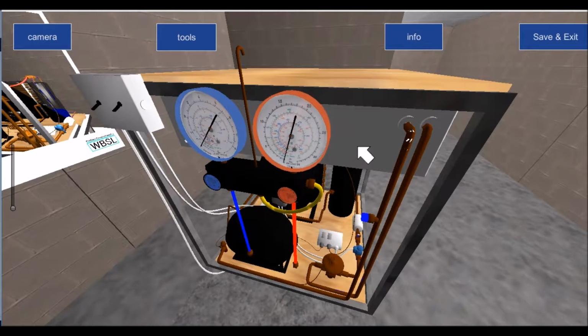So your evaporator then is the 4th component, and effectively what happens is that liquid is converted from a low pressure, low temperature liquid to a low pressure, low temperature vapor, and then it is superheated. In other words, the sensible temperature of the refrigerant is heated to a temperature above that of its saturation temperature. And basically that low pressure, low temperature superheated vapor is then drawn by the compressor back through the suction pipe back into the compressor, and the process starts again.